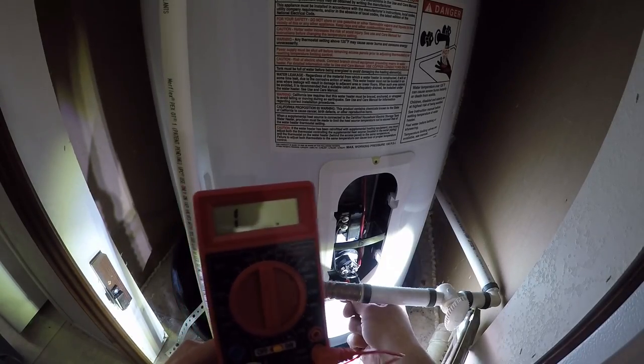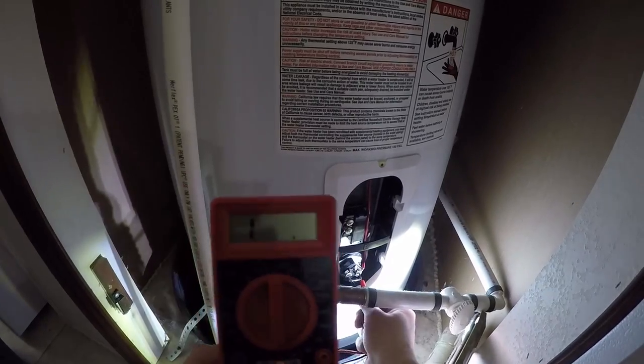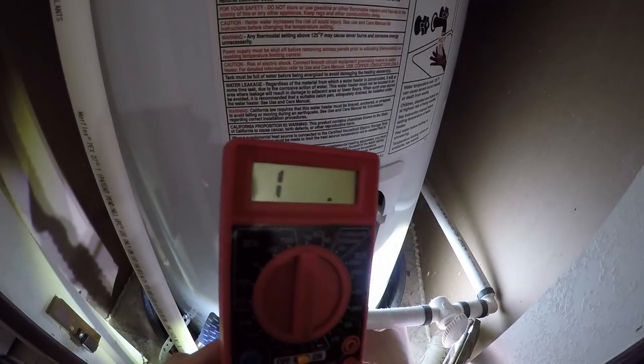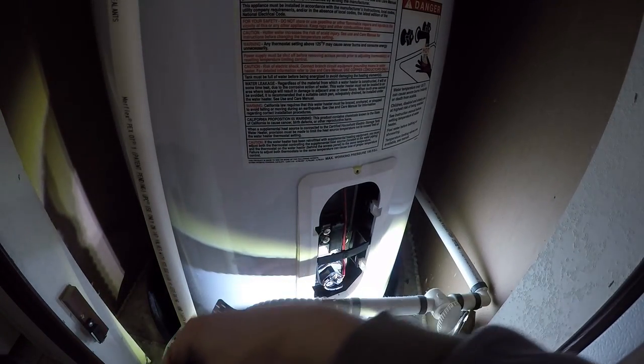This is what it actually looks like when you have a bad one. I have them down there, I'm pressing real hard and I'm getting nothing on the screen. If I flip them around — again, no difference. There's no reading at all coming from that one down there, so that's definitely a bad element.